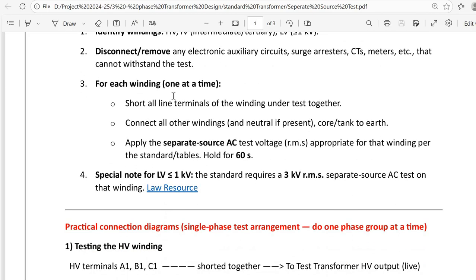For each winding, one at a time, short all line terminals of the winding under test together and connect all other winding, neutral if present, core and tank to earth. Apply a separate source AC test voltage of RMS value as per the standard tables and hold for 60 seconds. A special note for LV winding: if less than or equal to 1 kV, the standard requires a 3 kV RMS separate source AC test on the winding.